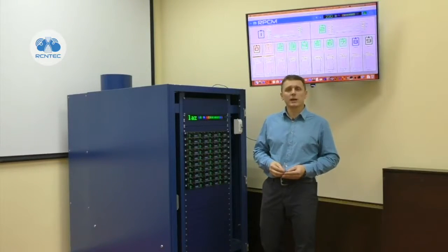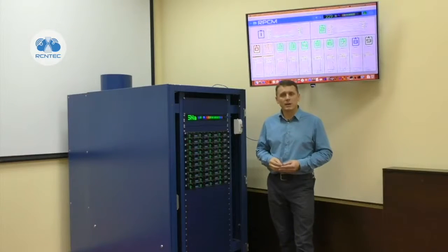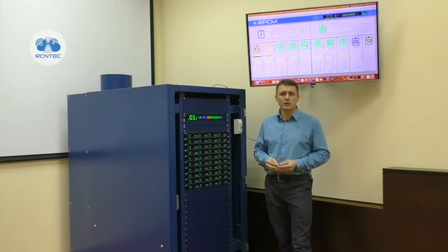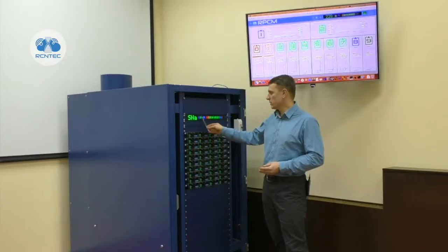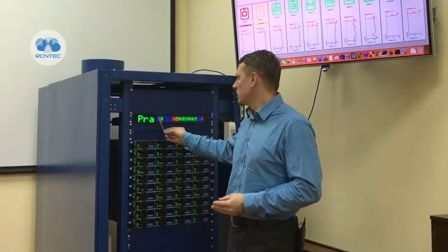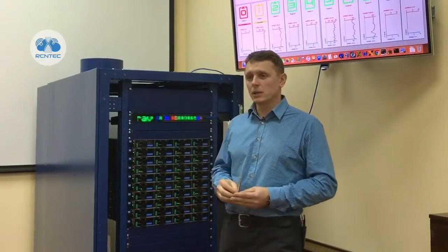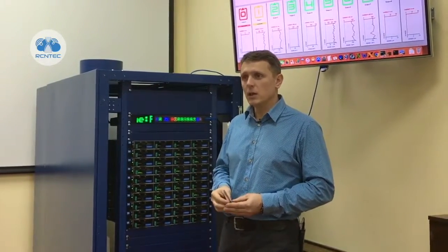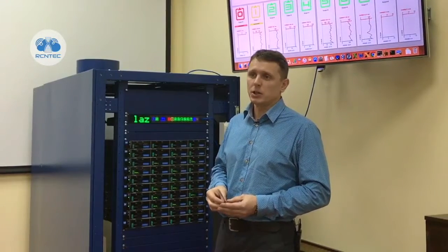Second important function of 16 amps and 32 amps RPCMs, the ones that have 2 inlets, is the automatic transfer switching. If power on main inlet gets lost, the RPCM automatically switches consumers to second inlet without interruption of power supply to consumers.